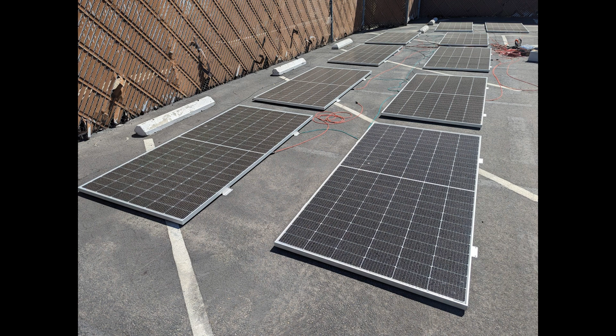Right now we have a test rig set up to de-risk solar panels directly feeding an electrolyzer, without any intermediate power conversion. The single biggest objection we hear to feeding raw solar direct current into our electrolyzer is that solar utilization is around 0.25, so our electrolyzer will need to throttle down overnight, and our electrolyzer utilization will only be 0.25.